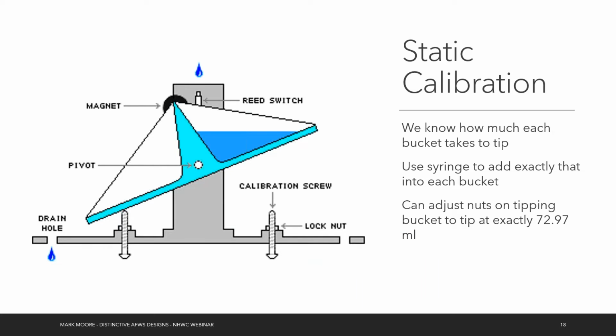Well, we can use that to do a static calibration, or maybe more accurately said, a static accuracy test. We know how much is supposed to tip in each bucket, and we can use a syringe on each side of that to make sure that it's working the way it should. Then we could adjust those calibration screws until it's getting exactly 73 milliliters in each tip on each side of the bucket.